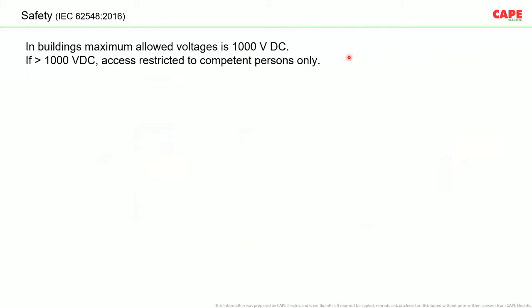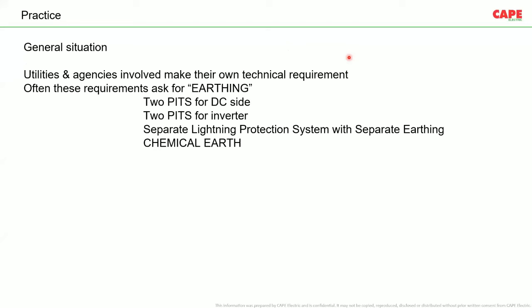Yeah, the first part with respect to safety is the rooftop system. Maximum voltage allowed is 1000 volt DC. If more than 1000 volt DC is used, the access must be restricted to competent persons only. That means only the technicians should go to that particular area. There are buildings nowadays with more than 1000 volt DC, but most of the time these are rooftops in large industrial areas, and there only the technicians are going, technicians with the proper PPEs.